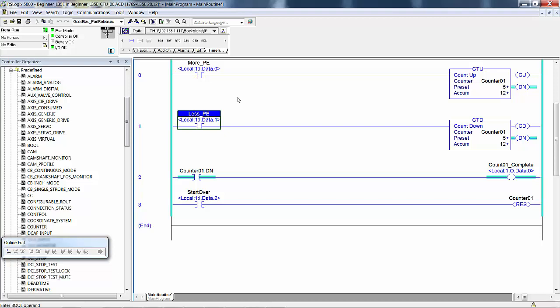With the timer data type, when it's done, it's done. It's not going to go any further. It's not going to count any more units of time under any kind of normal circumstances. However, with the counter, it just keeps on counting up until you hit, what was it, 2 billion and something. The done bit is on anytime the accumulate is equal to or greater than the preset, then the done bit will be on.